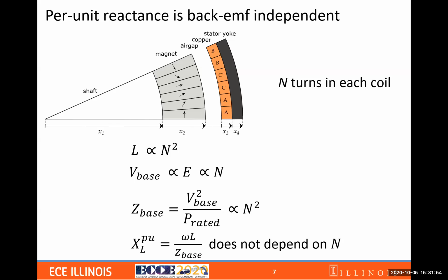That is because the generator per unit inductance XLPU is independent of the number of turns in each coil, and also independent of the terminal voltage. So in particular, if you consider a generator here, and in each coil in the generator there are N turns, the coil inductance is proportional to N squared. And if we calculate the base impedance, Z base, it is again proportional to N squared. And when we consider the per unit reactance, it is the reactance of the coil divided by Z base, which turns out to be independent of N.